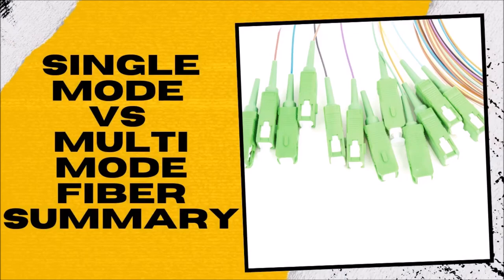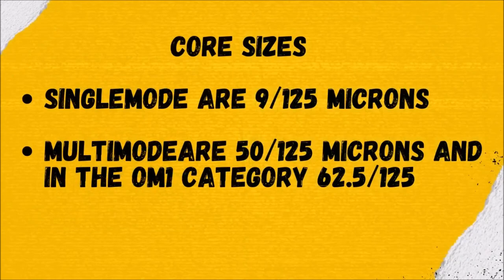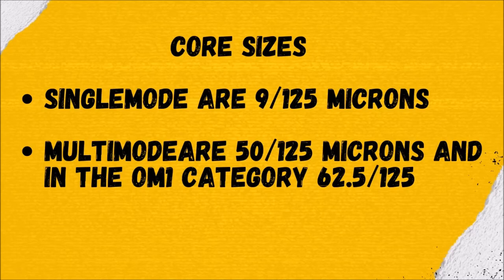Single mode versus multimode fiber summary. Core sizes: single mode are 9 by 125 microns. Multimode are 50 by 125 microns, and in the OM1 category 62.5 by 125.